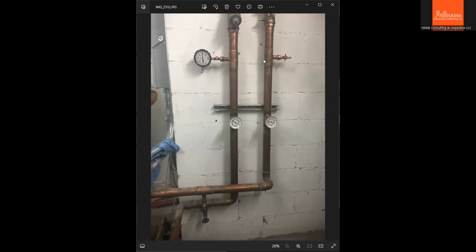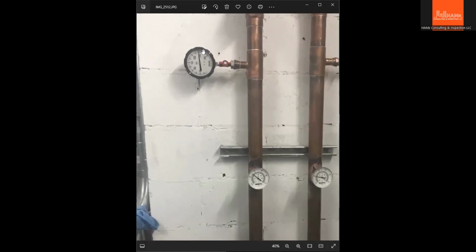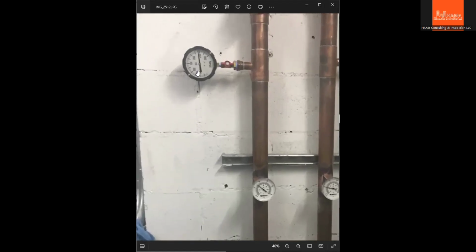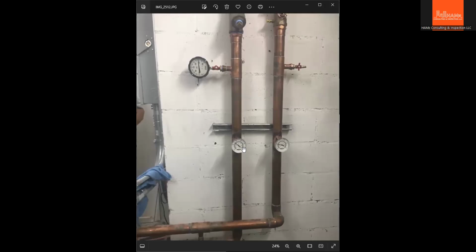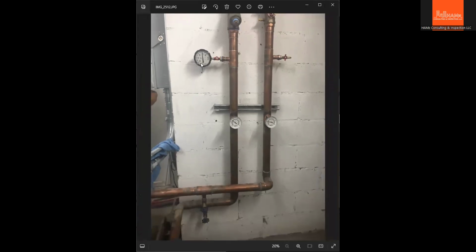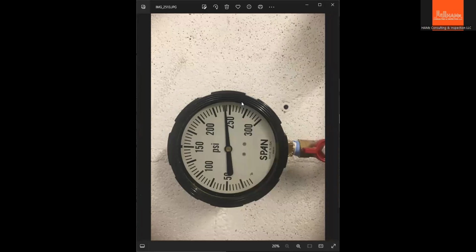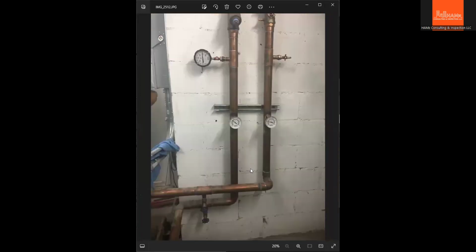So I believe this pipe is looped together so that we only put one pressure gauge. What I mean to say is if it's looped together, it's connected to each other at the other end of the pipe or in the unit. So we're only observing the pressure at one side of the pipe because this pipe is connected to this also. So we're testing it as one system. But when it operates, it should be the supply and return.